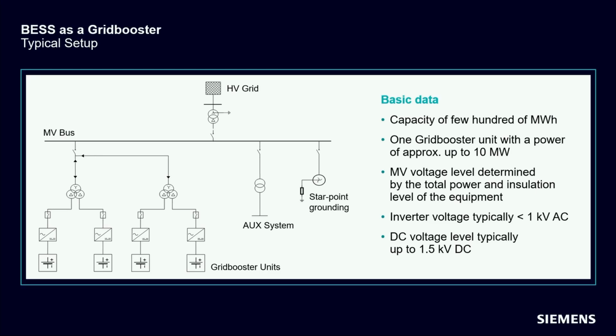All grid booster units are running in parallel and feeding a medium voltage bus configured as a single or double busbar. The medium voltage level is determined based on the required power, insulation level of the equipment, and economical aspects. From the medium voltage level, the power is then transferred through a large step-up transformer that is connected to the high voltage grid. In Europe, this is typically the 400 kV voltage level.